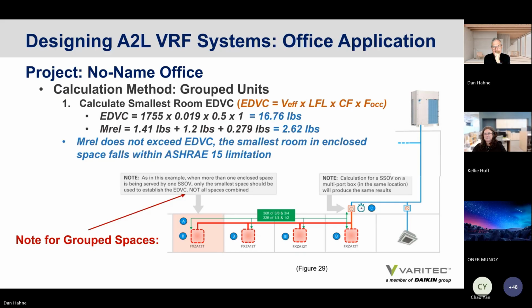From Daikin's standpoint, if you're talking about the location of the safety shutoff valve for heat recovery, that will be downstream of the existing EEVs in our BS boxes. So that will be between what you would interpret as the current BS box and the indoor unit, if you're talking about the location of that valve. But it will be integral to the design of the BS box for heat recovery.